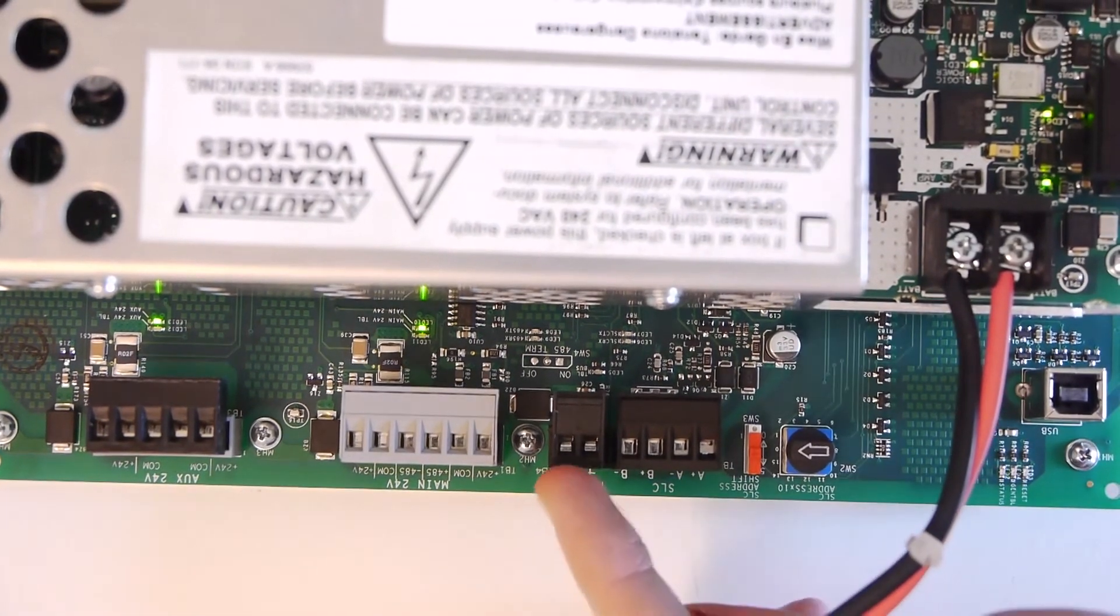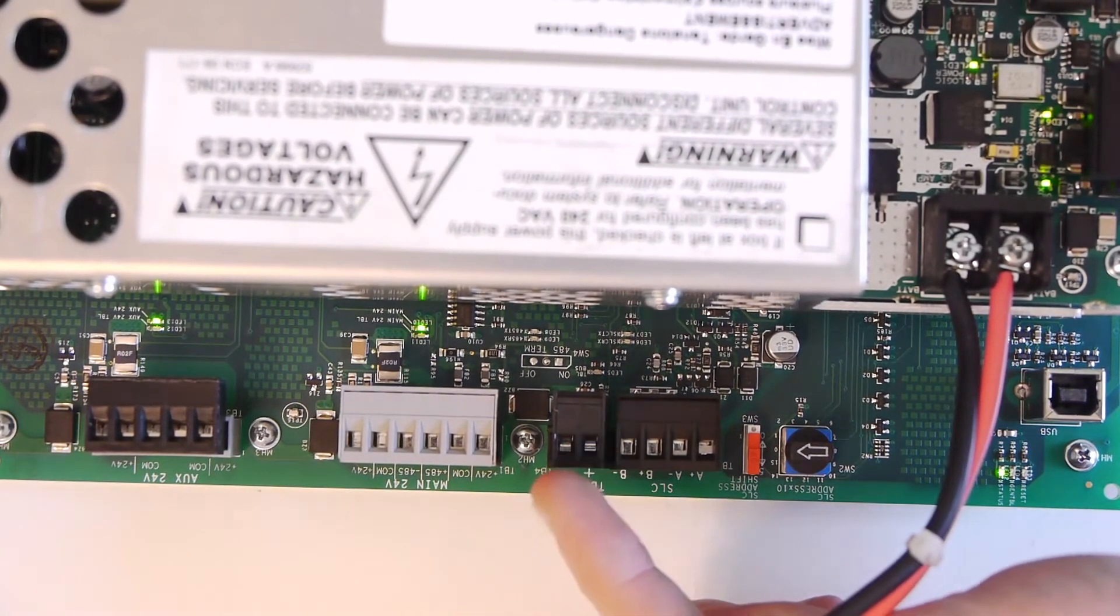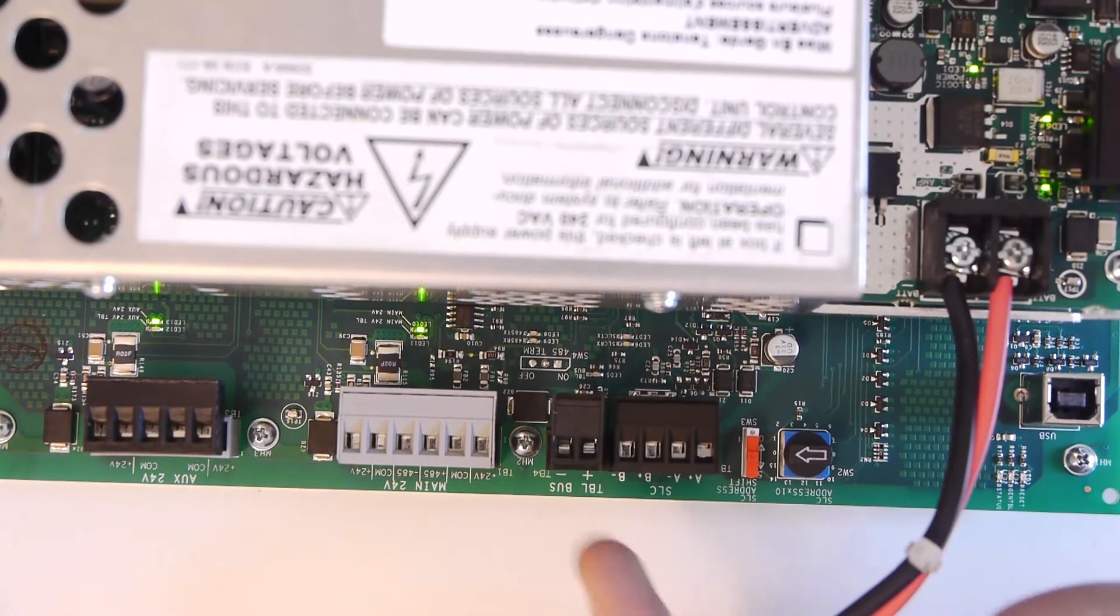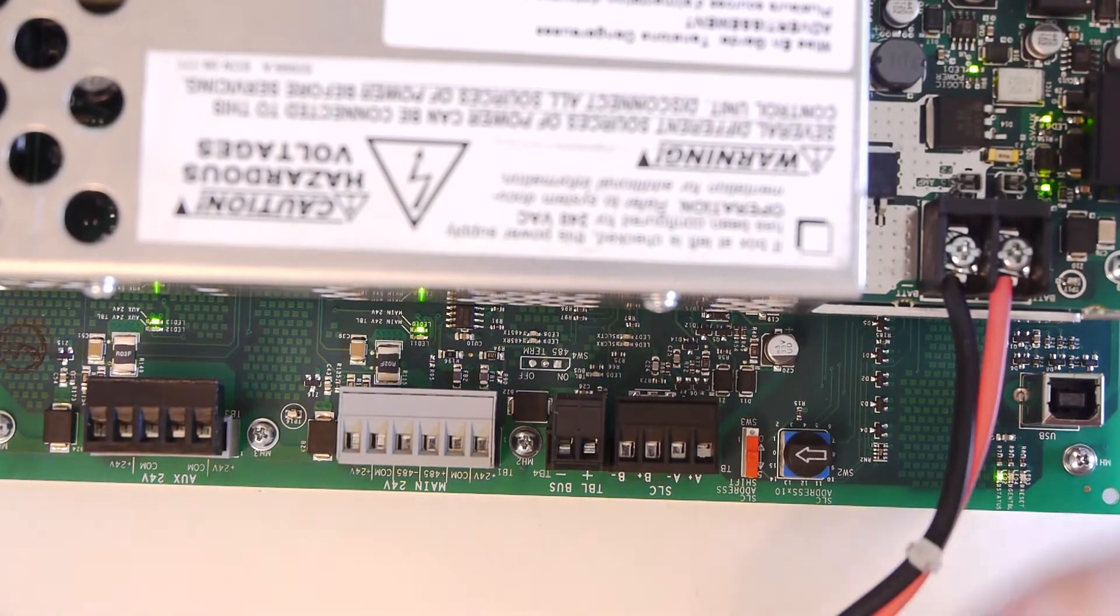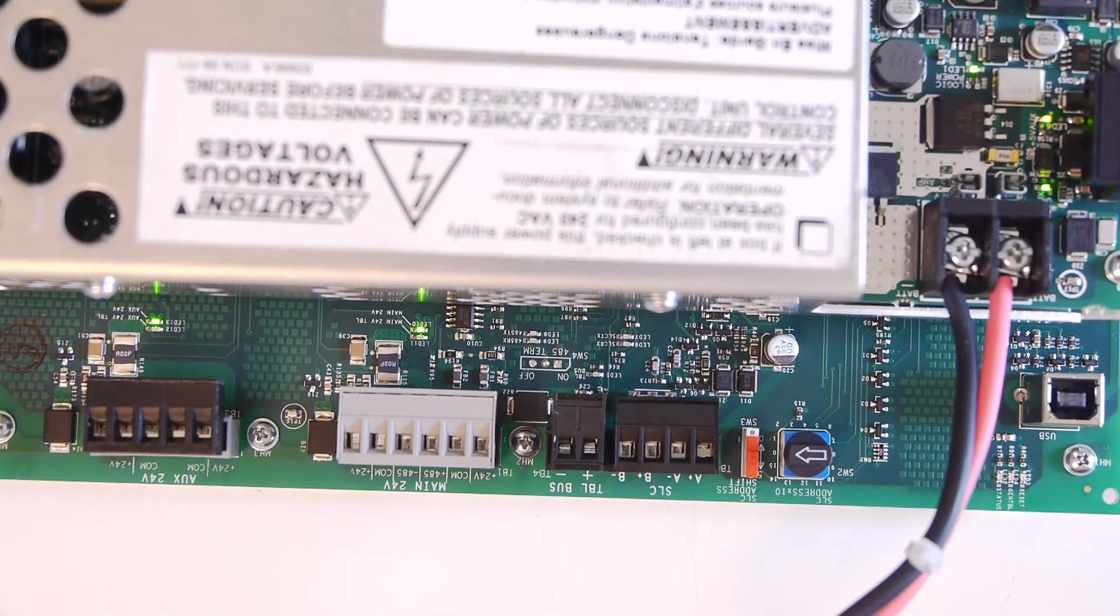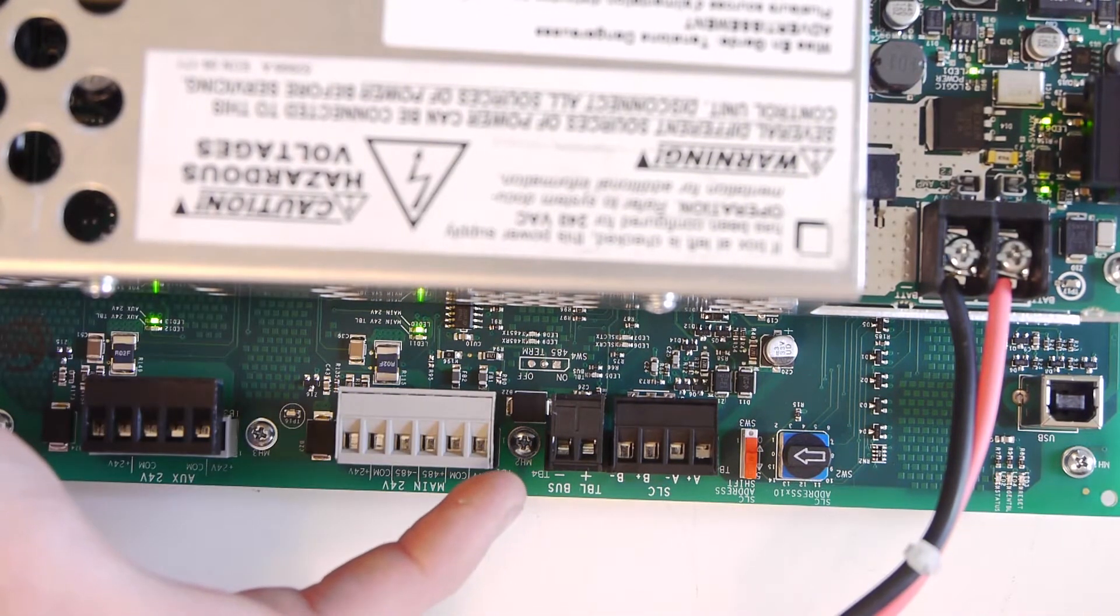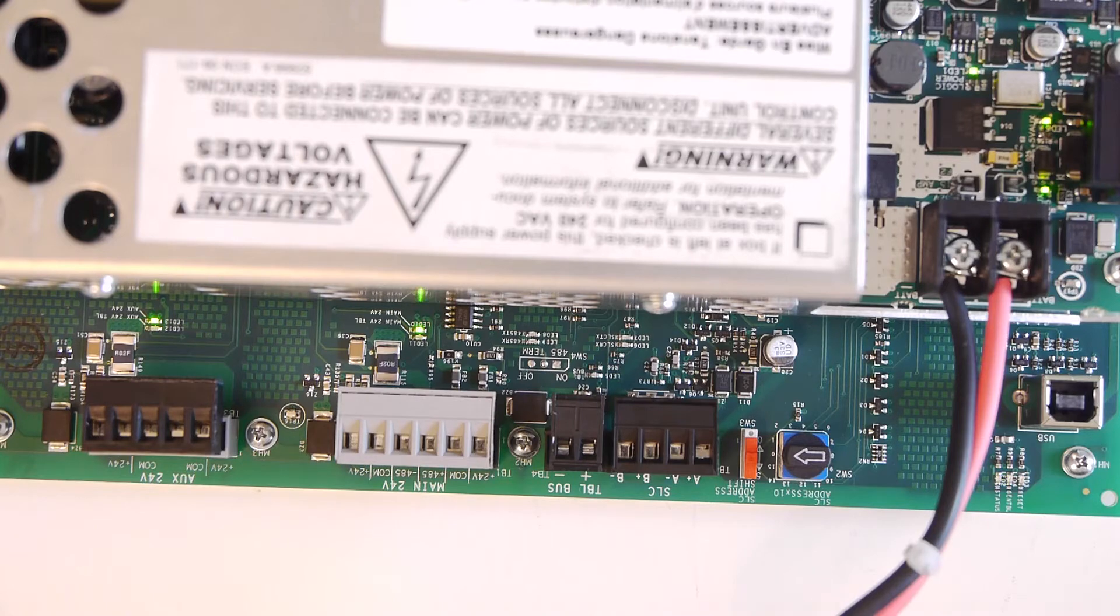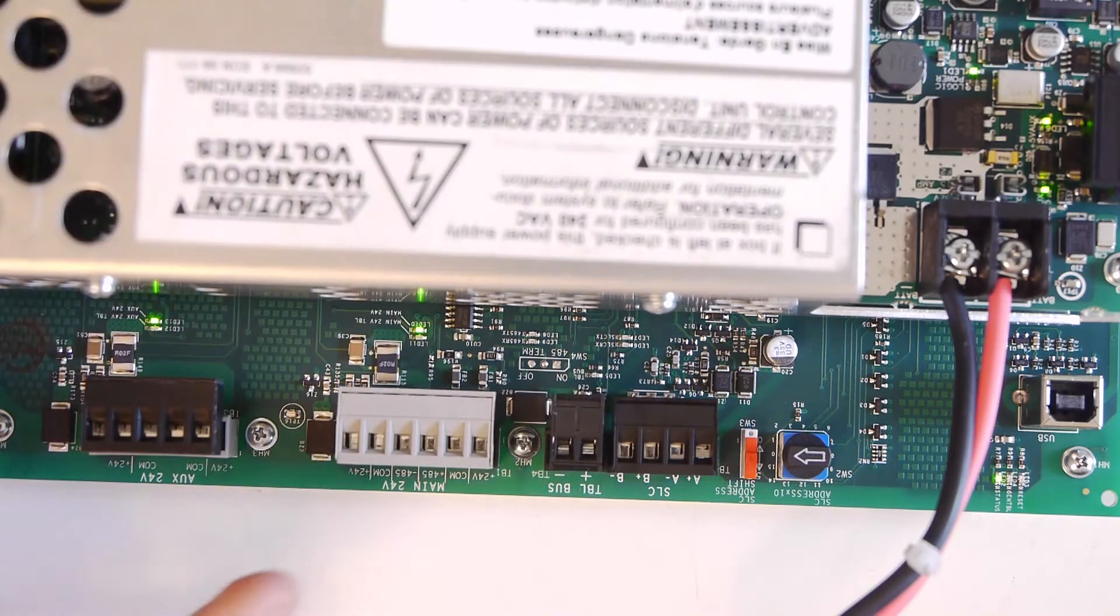Right here is basically an auxiliary trouble input. So if you short these two terminals right here, it'll bring up a trouble light on here. And I believe once this is connected to a fire panel, it'll actually bring up a trouble on the panel. Just a general trouble. An example of how you'd use that is you connect that to a surge suppressor with a contact. So if the surge suppressor realizes that it blew, then it would close the contacts and it would tell the panel there's a trouble.